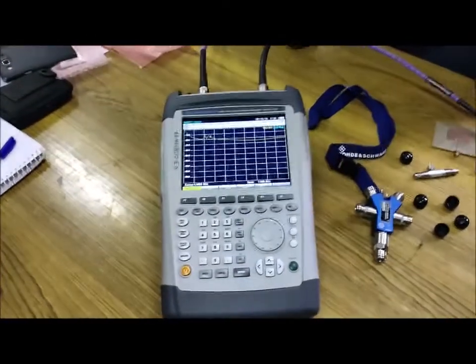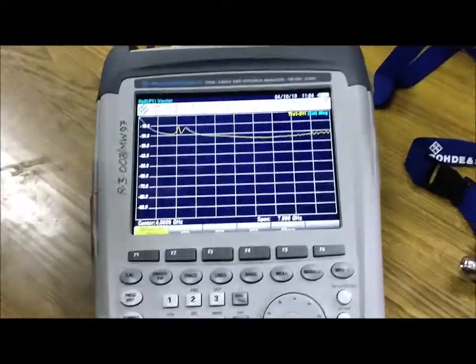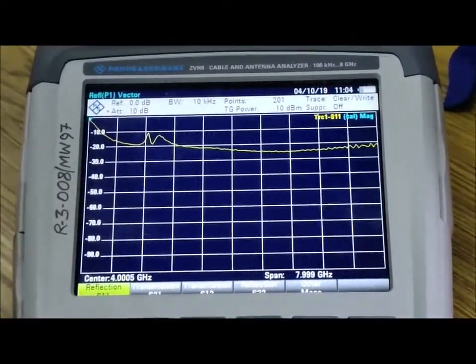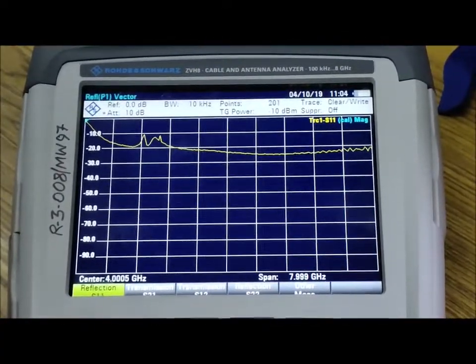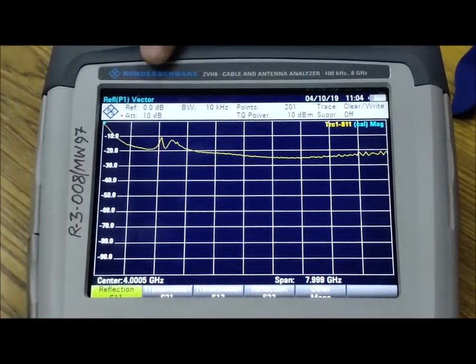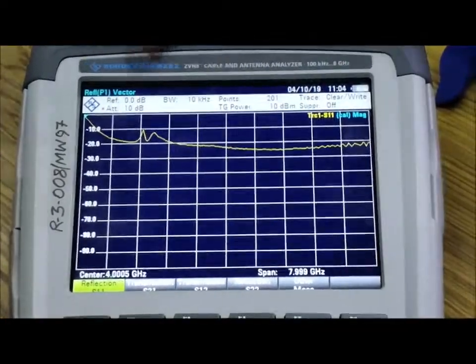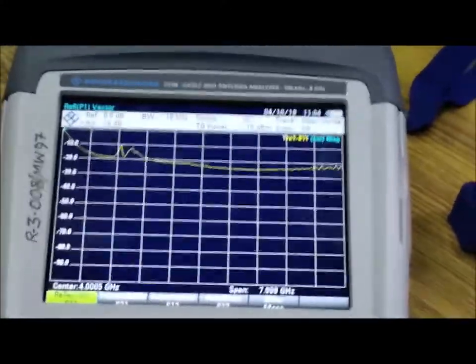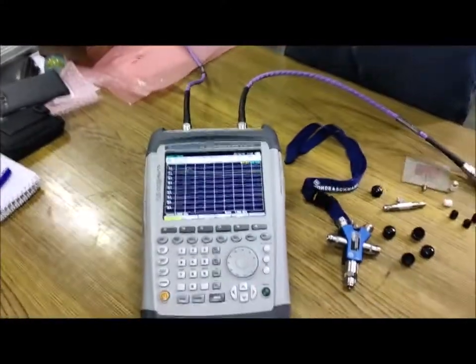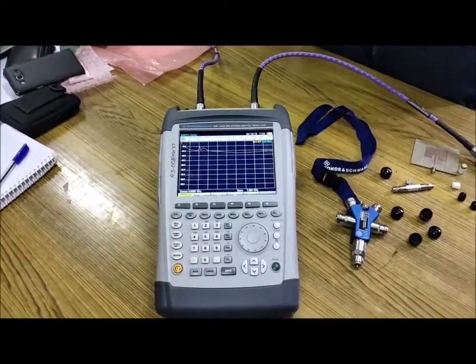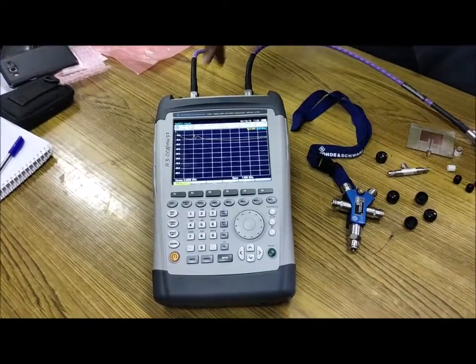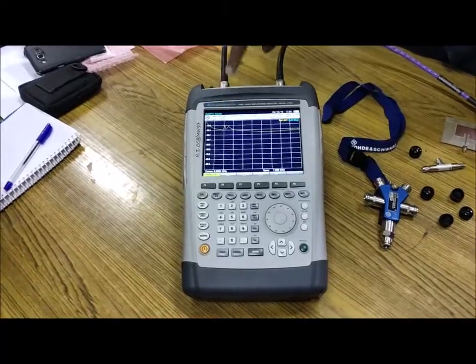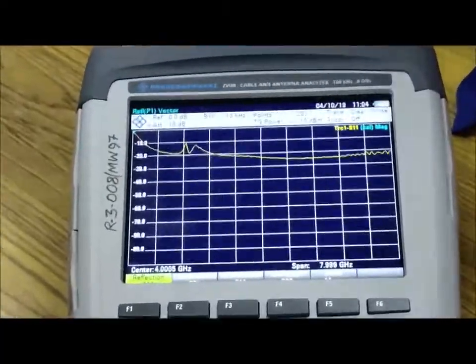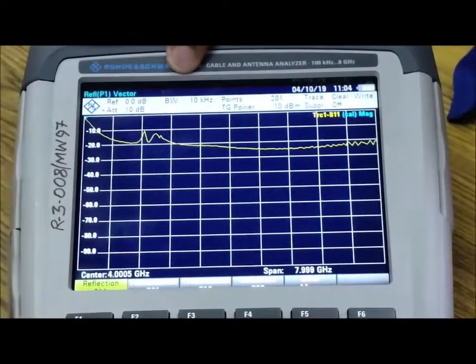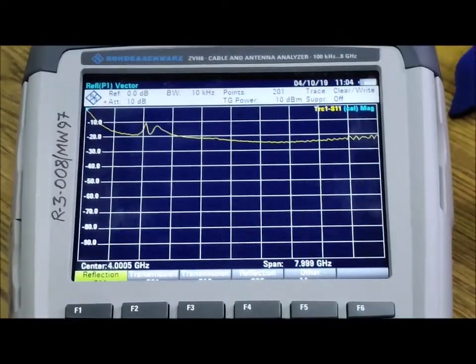And now the display will show you the value of whatever the display we can see. The reference level is 0.0 dB. Normally the short is having the 0.0 dB. That is the reference level. It is selected for return loss measurement of the DUT. Attenuation right now is selected at 10 dB, so any power which is separated is again reduced by 10. Just to show, this is the bandwidth, 10 kilohertz.